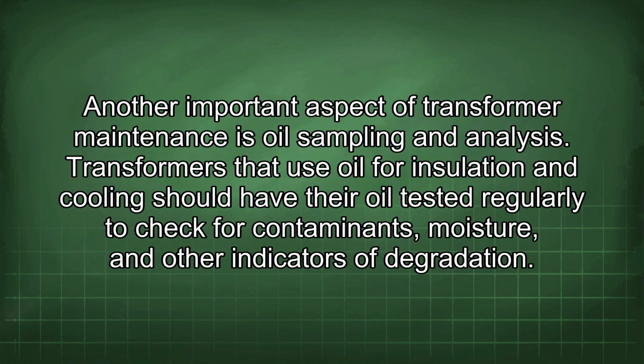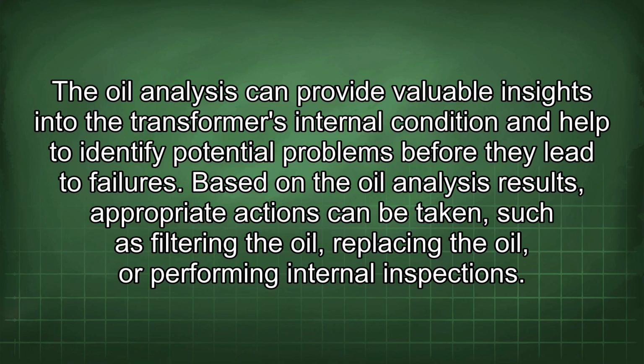Another important aspect of transformer maintenance is oil sampling and analysis. Transformers that use oil for insulation and cooling should have their oil tested regularly to check for contaminants, moisture, and other indicators of degradation. The oil analysis can provide valuable insights into the transformer's internal condition and help to identify potential problems before they lead to failures.